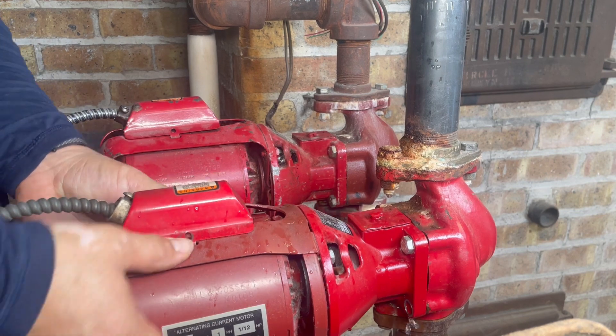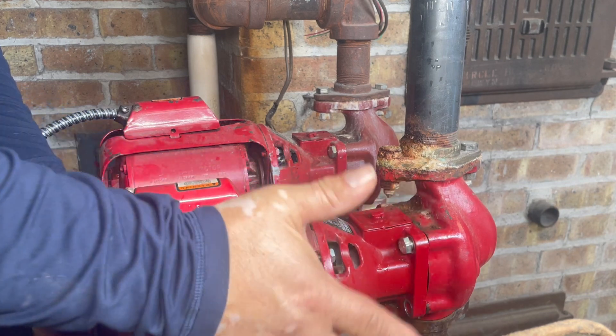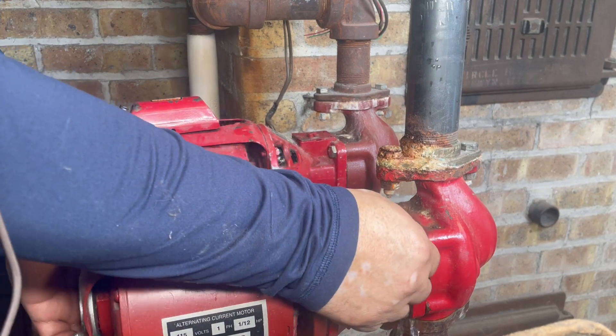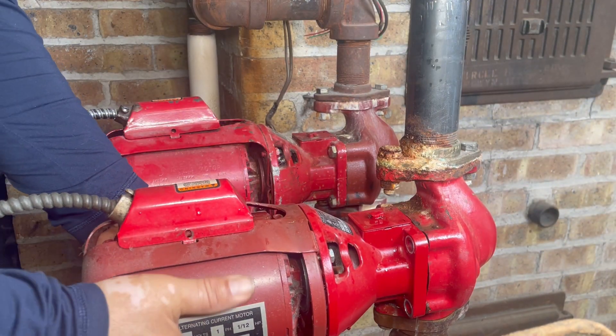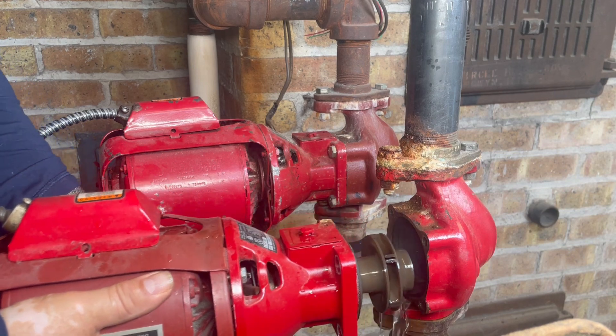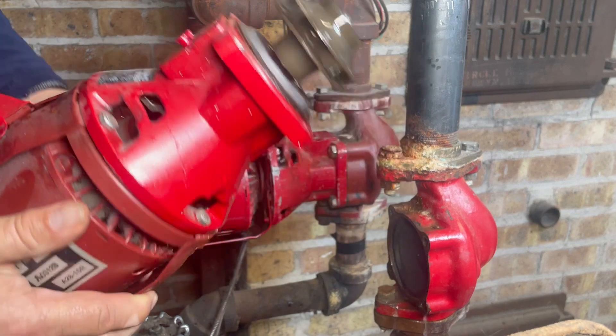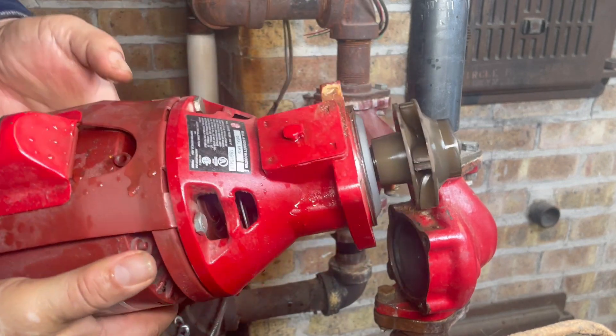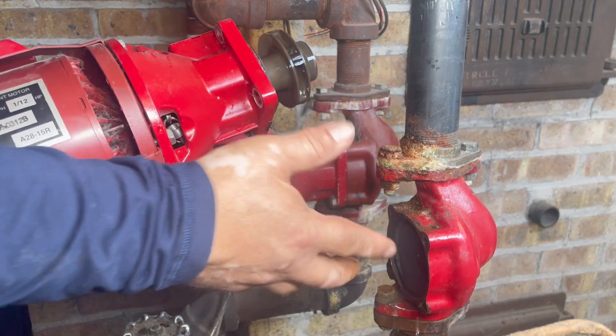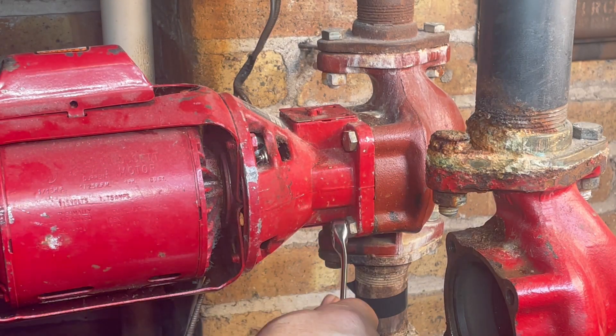That wasn't much water. Now I'm going to remove the last screw, grab the pump, and put it out of the way on top. There are no more screws — I can pull it out. The impeller on this first one doesn't look that bad, but this is the good pump. We're going to replace both since it's all rusted — we want to service both at the same time.